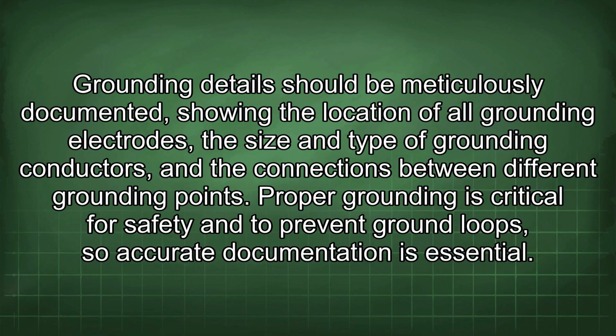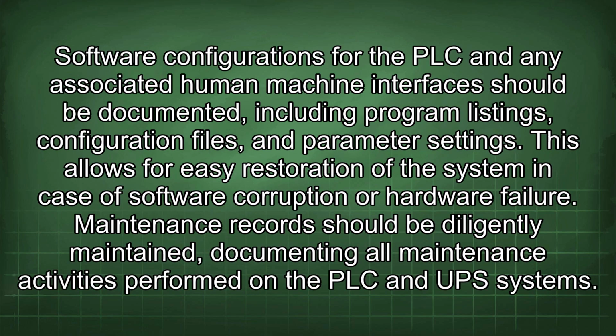Grounding details should be meticulously documented, showing the location of all grounding electrodes, the size and type of grounding conductors, and the connections between different grounding points. Proper grounding is critical for safety and to prevent ground loops, so accurate documentation is essential. Software configurations for the PLC and any associated human-machine interfaces should be documented, including program listings, configuration files, and parameter settings. This allows for easy restoration of the system in case of software corruption or hardware failure.